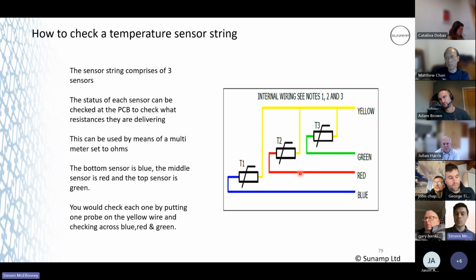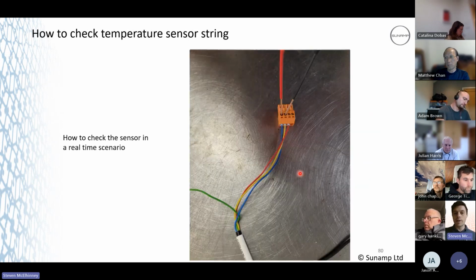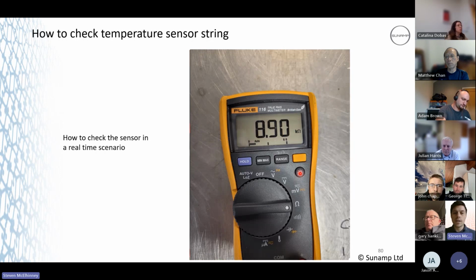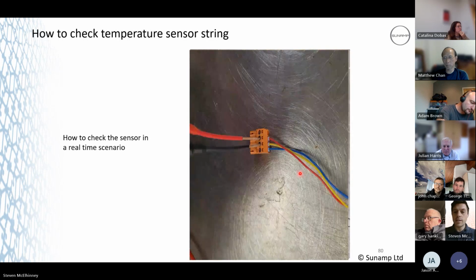So, you just want to make sure that everything's working correctly before you leave. So how do you check it? Set your multimeter to resistance, yellow across blue, 8.9 kiloohms. So this is a temperature sensor sent out from a battery. So when I've done this test, this is the ambient conditions that the sensor is being tested under. So yellow across blue, 8.9.